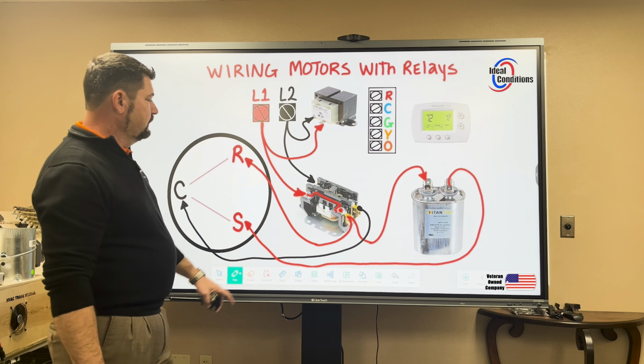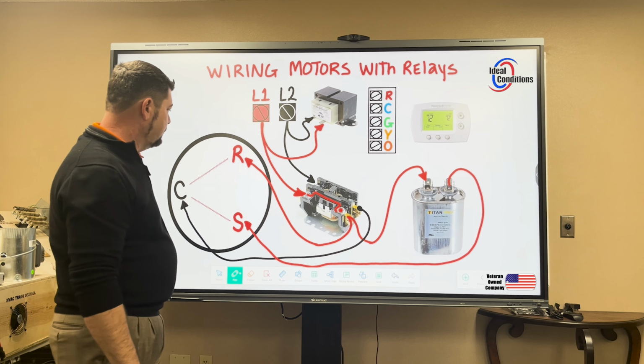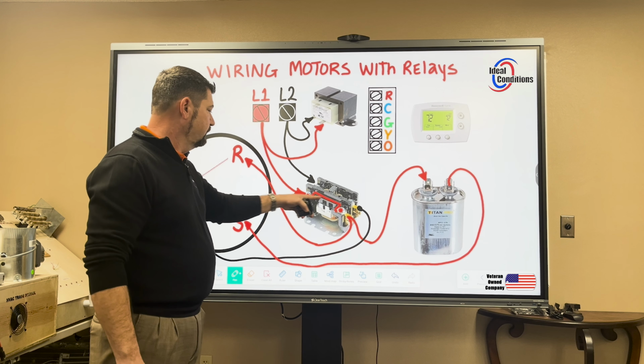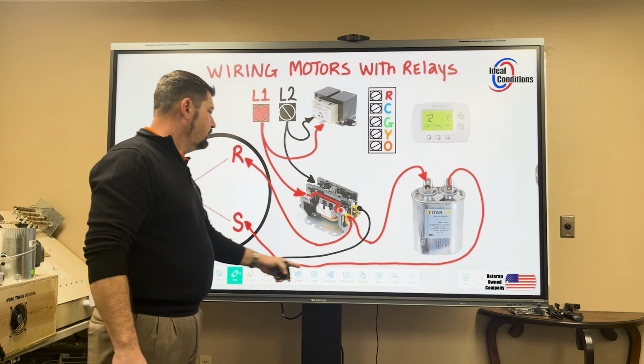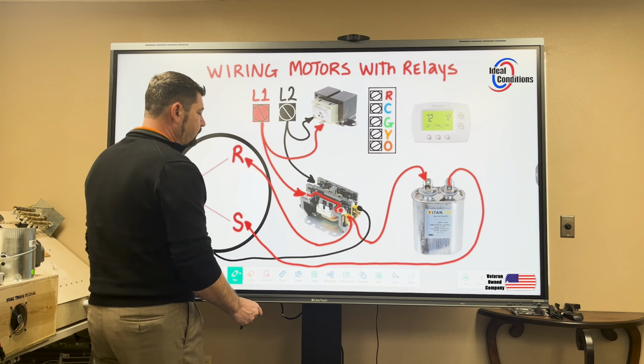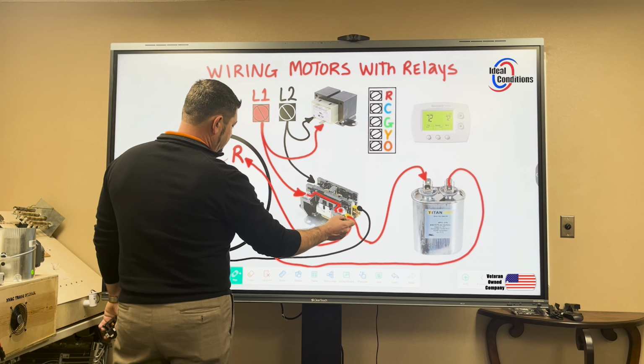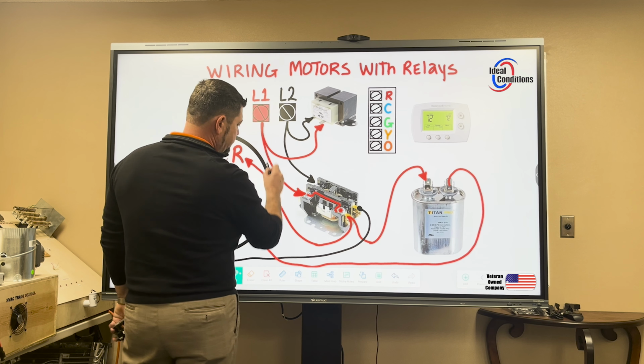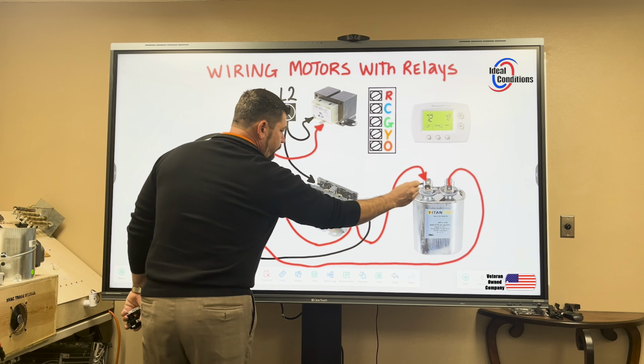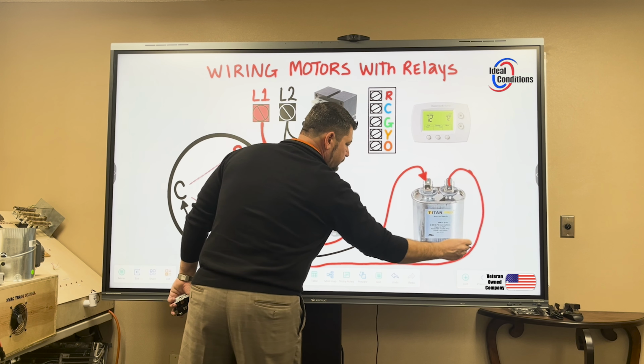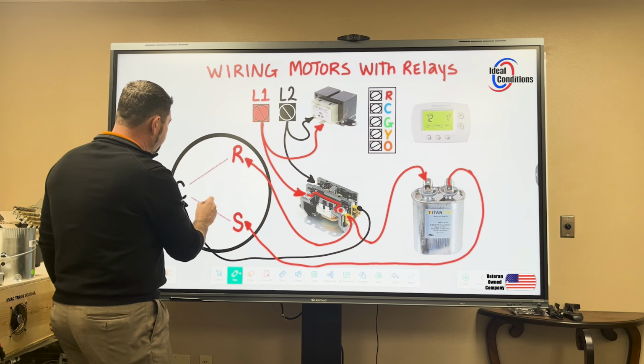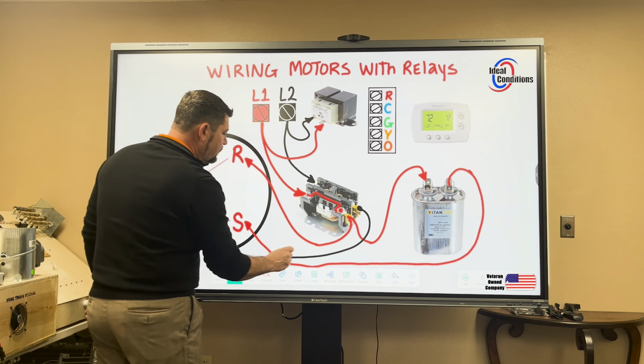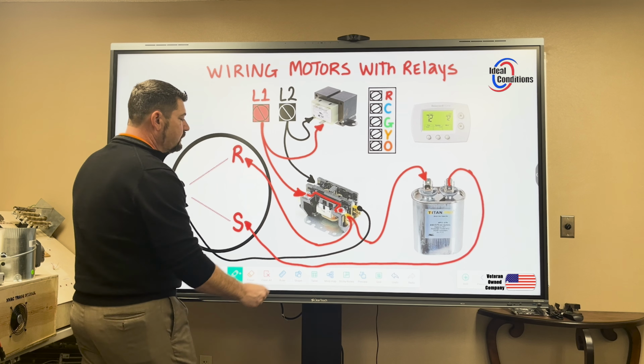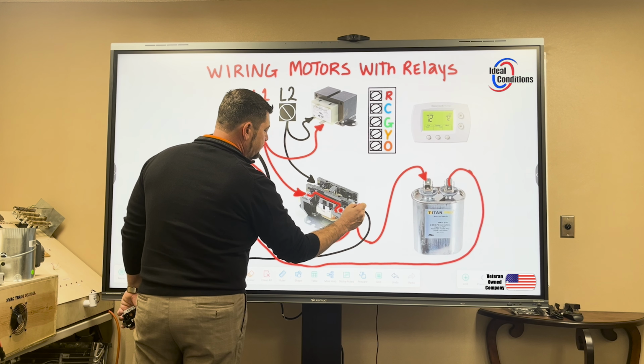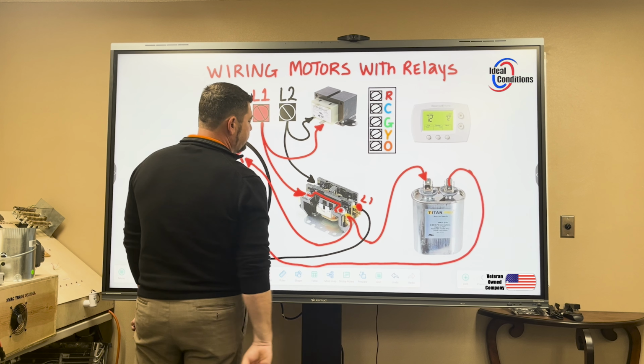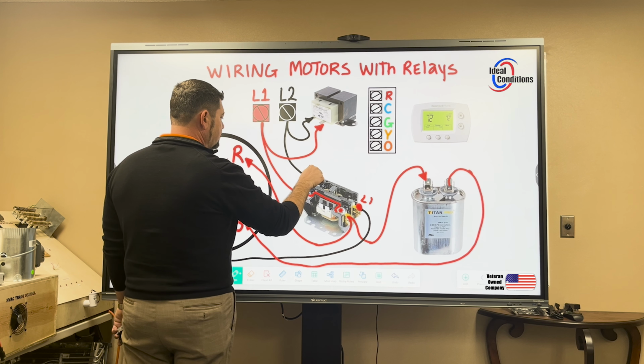Now this contactor right now is still not energized, so I still have L1 present all the way back to here. It's also present back to here because it did this. Here's L1 through my capacitor, all the way to my start winding, back up to my common winding, all the way back over to here. So no matter what, I am technically at L1 here until I get power.